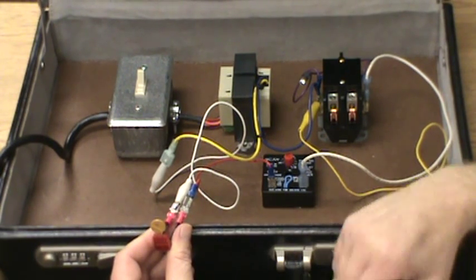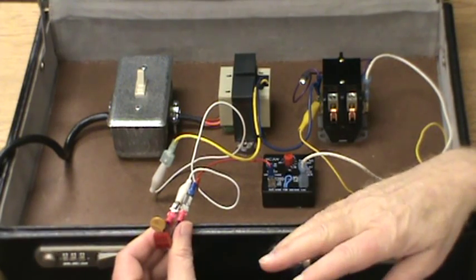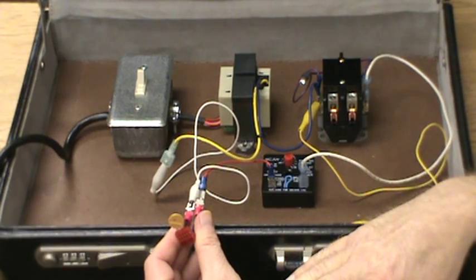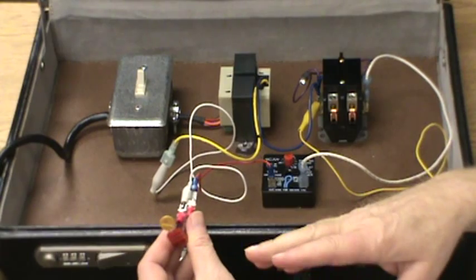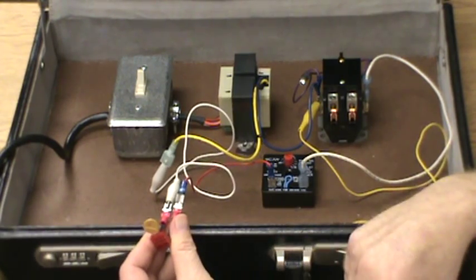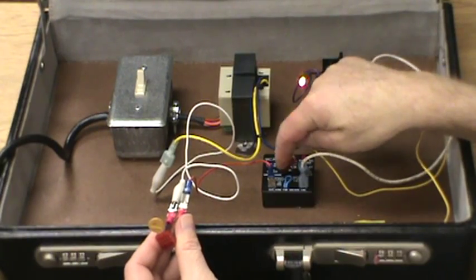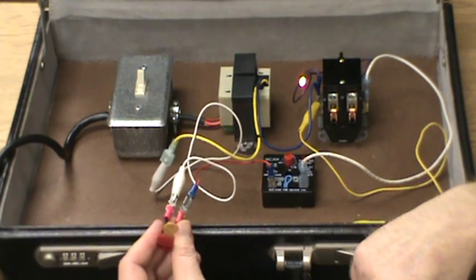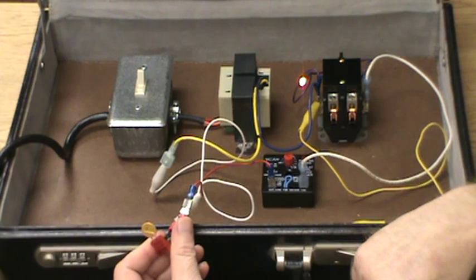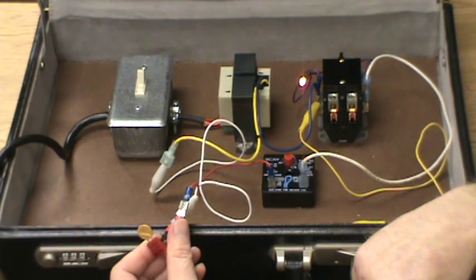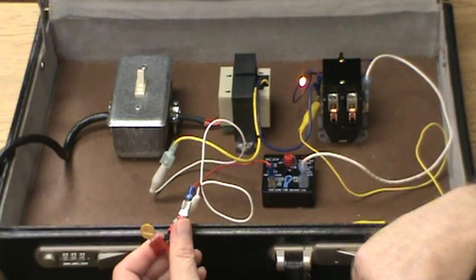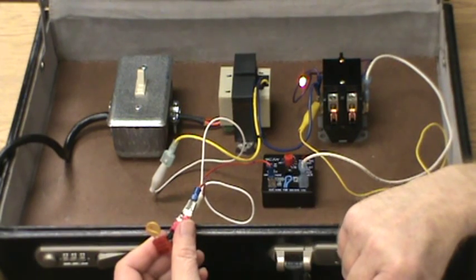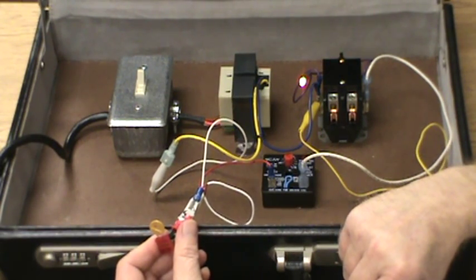It'll go ahead and, if it's an intermittent short that lasts for a few seconds, or wires that touch - doesn't make any difference - once that fault condition is cleared or those wires aren't touching anymore, it'll automatically reset just like that through the time delay. You don't have to make another trip or go back to the customer's house. It'll trip to protect everything, then reset automatically through the time delay. That's about it.